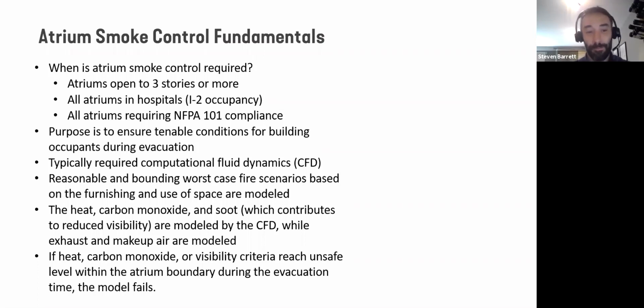Typically, this requires computational fluid dynamics analysis. And what we do is we take a reasonable and yet bounding worst case fire scenario in the atrium boundary based on the furnishings and the use of the space. We model that fire to determine the heat, the carbon monoxide concentration, and the production of soot, which contributes to reduced visibility in the CFD model, while simultaneously air is being exhausted and made up.